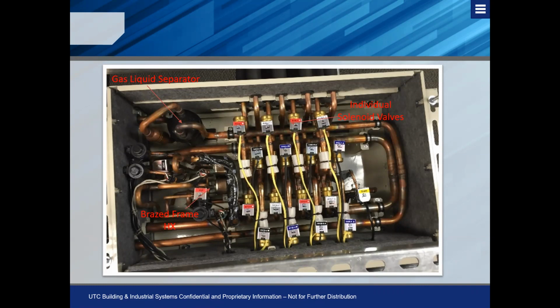A nice unique advantage that we have is this box being fully serviceable. The other VRF manufacturers typically insulate this entire box, which means they don't have to have a drain port, which often is a nice selling feature depending on where you're locating this box. Typically, what you'll see is there are extra ports on competitive products that are left open, because if a solenoid does fail, they can't get any access to replace it. So they have to leave an extra port, and move the failed solenoid valve to the extra port that they left during the design. With us, you can go in and directly replace individual parts without having extra ports. And you may require a drain, however, that drain comes at a very cheap cost given the fact that you have to get in here and work on this box. Typically we don't see that, but it is nice to have that serviceability and accessibility.